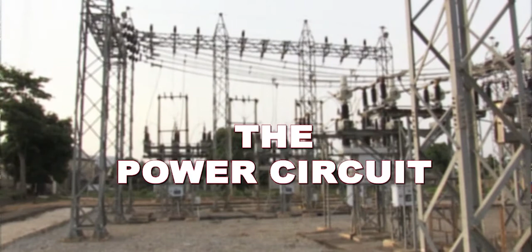This is New Apo in Abuja, where the Transmission Company of Nigeria, TCN, is building a brand new 330 kilovolt transmission substation, a mega project under the Abuja Feed-in Scheme. This will be the third 330 kilovolt transmission substation after the Katampe and Gwagwalada substations within the Federal Capital Territory, FCT. The construction of a switchyard for this substation has advanced with materials on ground to accelerate its delivery.